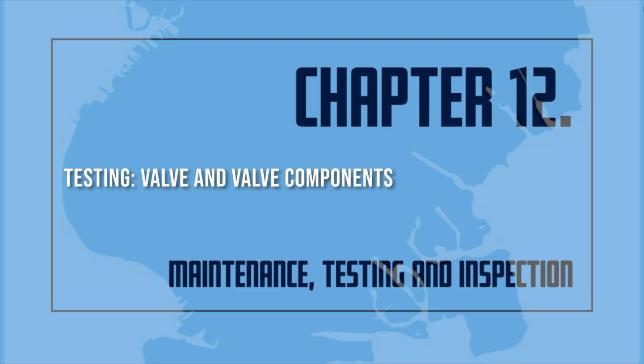2. The system air or nitrogen pressure and the supply water pressure are recorded. 3. The system air or nitrogen pressure is relieved by opening the inspector's test valve completely. Concurrent with opening the valve, both testers start their stopwatches. If two-way communication is not available, the tester at the dry valve is to react to the start of downward movement on the air pressure gauge.